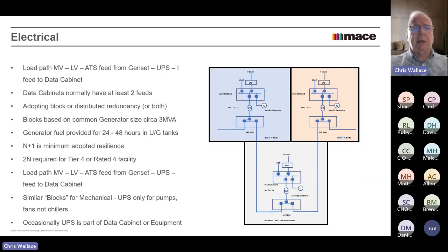But anyway, going on to the next slide on electrical, what I described on the last slide, the ring main units, you can see those are at the bottom of each of these blocks here. And you see, one in, one out, and one spur. Again, I've used the red and the blue to show you that they may be from opposite ends of the ring. And what you then do is you come from the MV ring main unit into the transformer. And bear in mind, these are just very, very diagrammatic.